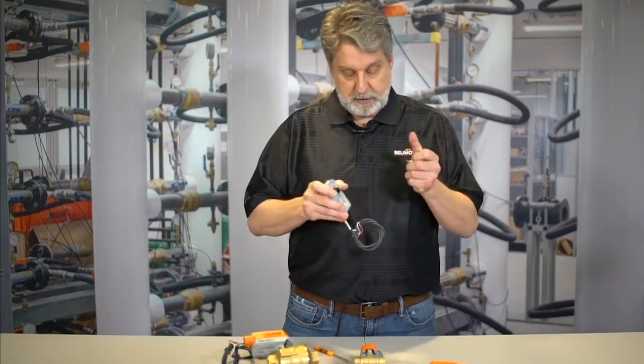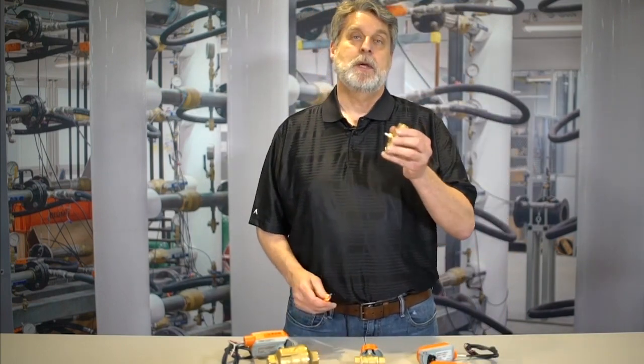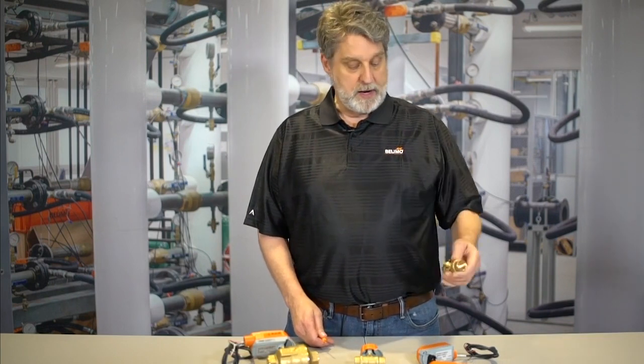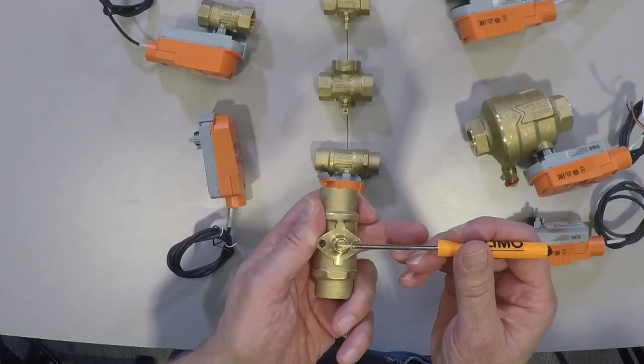Now, I'm telling you you shouldn't turn or twist it, but let me show you an example of what could happen on a job site. Pipe fitters come in, they separate the actuator from the ball valve. When we separated this, the ball valve is in the closed position.